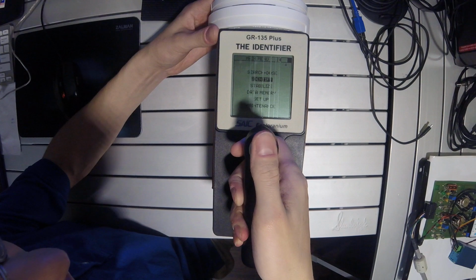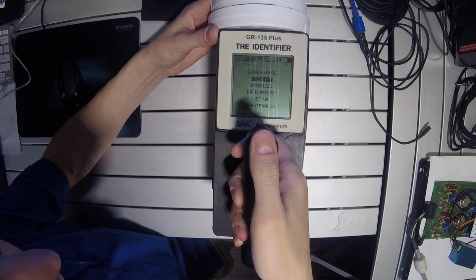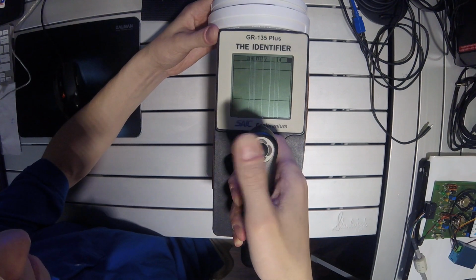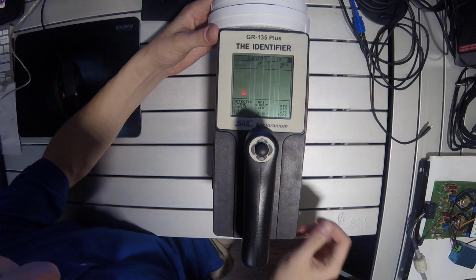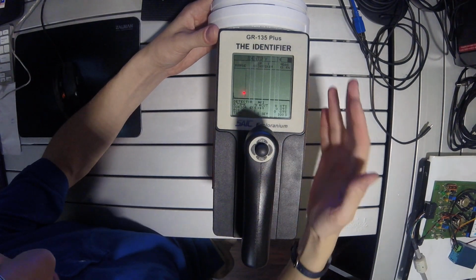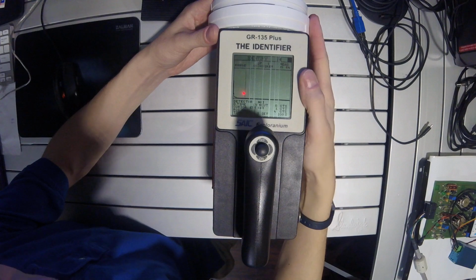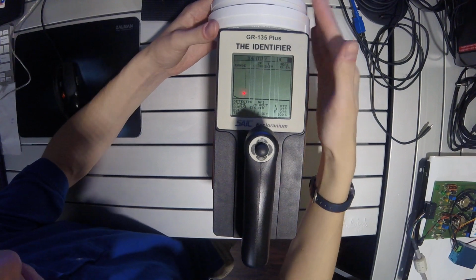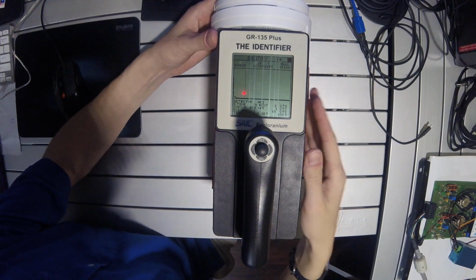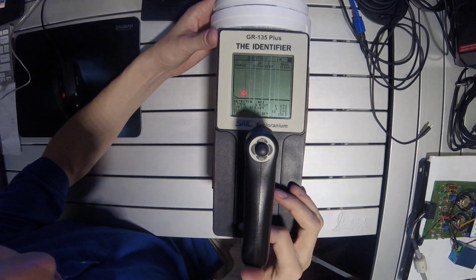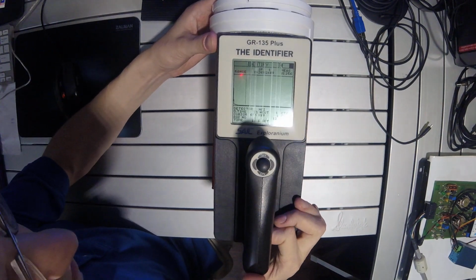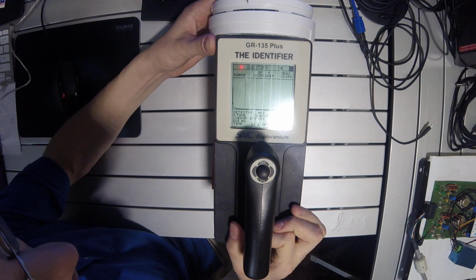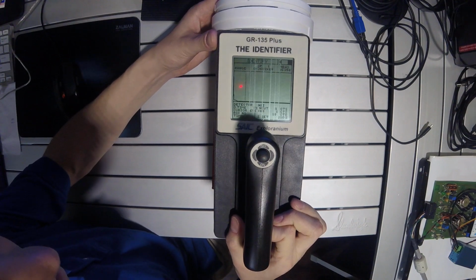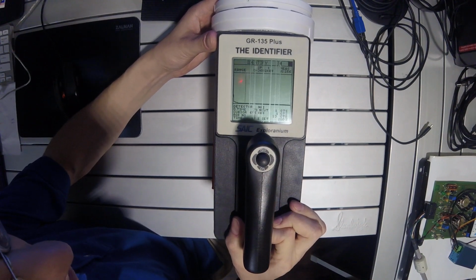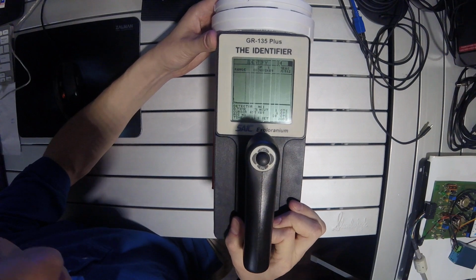However, the unit is sensitive enough, if we go to identify, it will be able to pick up the americium gamma ray spectrum, even for a source as weak as a smoke detector. This will take a little longer to accumulate, so I'll give around 30 seconds to integrate up that spectrum.